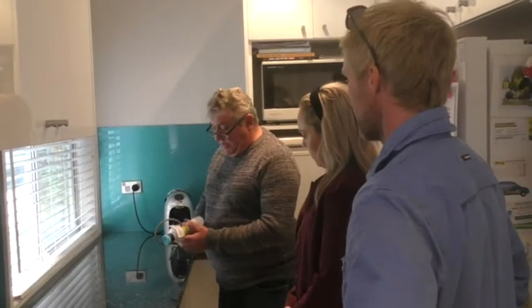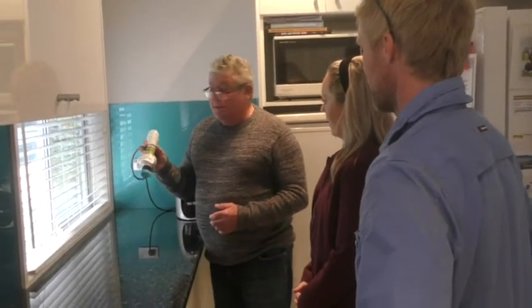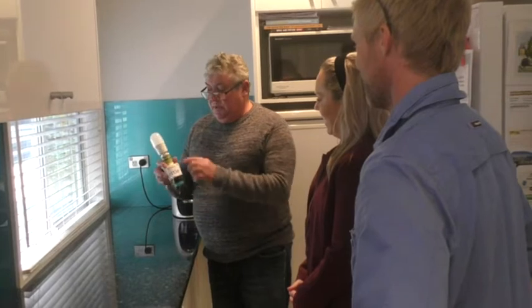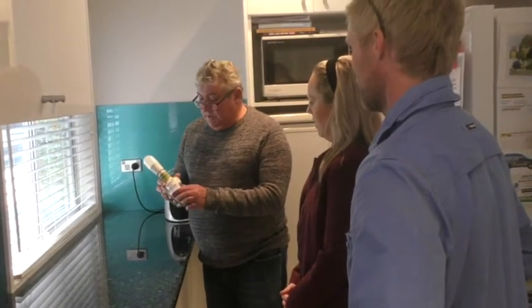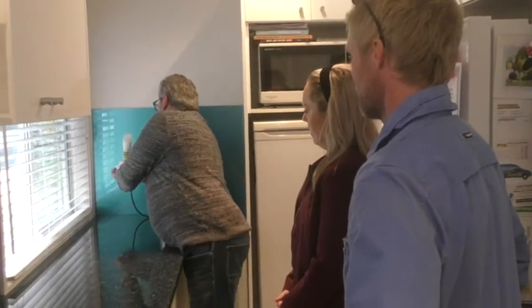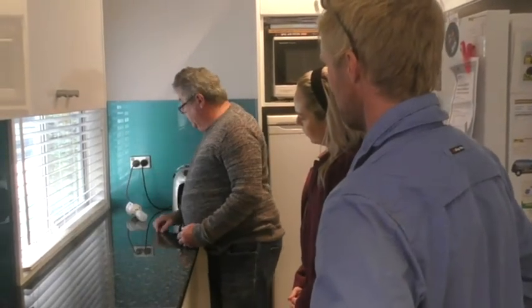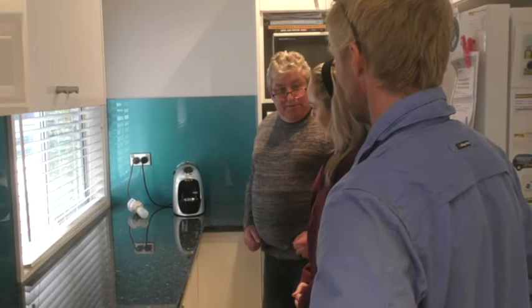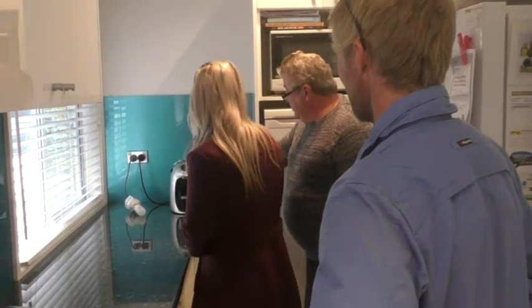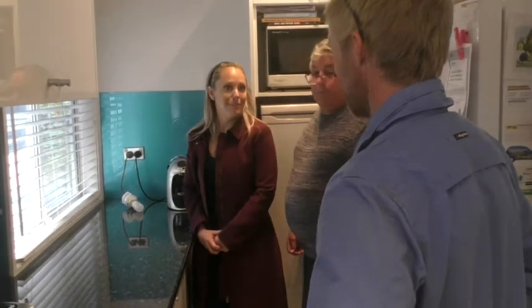Okay, we're in the kitchen and we have this piece of technical equipment that simulates an active-to-earth fault. We're going to plug that in over here — that simulates our kettle. Just turn the switch on. The power has tripped off.